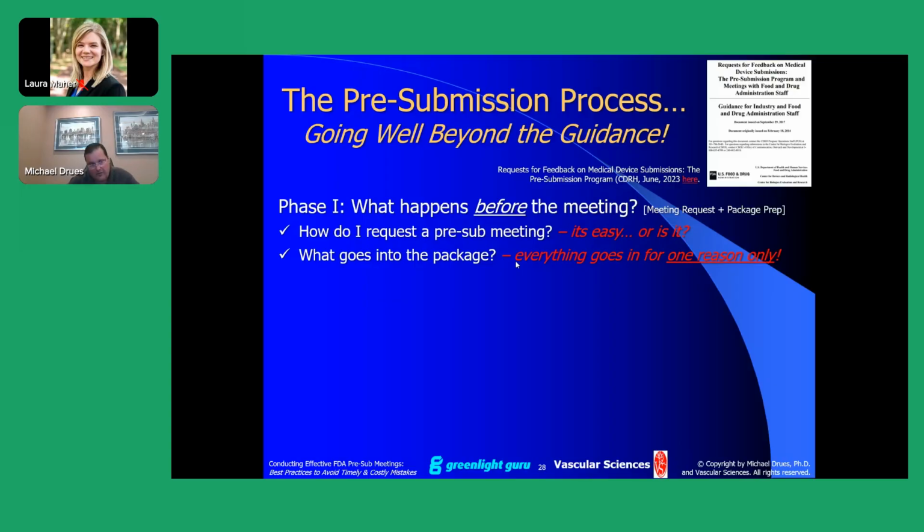In other words, I talked about the questions a moment ago. In the pre-sub guidance, FDA lists dozens and dozens of example questions. I will never in a million years use any of them. I think they are absolutely terrible questions for a variety of reasons. Instead, as my attorney friends like to say, I always phrase my question as a leading question. In other words, I want them to come to the answer that I want them to come to.